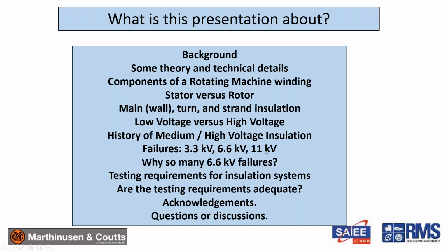And then we look at this: I work in the repair industry, and we've noticed that we see a higher ratio of 6.6 kV stator failures from most OEMs, in fact, if not all, depending on how well they are represented in Africa and South Africa. And the failures are over a particular period, from about 2 to 5 years, so outside the warranty period, but way too early to be considered normal operation. And then I asked the question, why so many 6.6 kV failures? Why is this not picked up by the testing requirements? I'm talking about not the routine tests, but type tests, and specifically the thermal cycling test at elevated voltage. And then, are the testing requirements adequate?